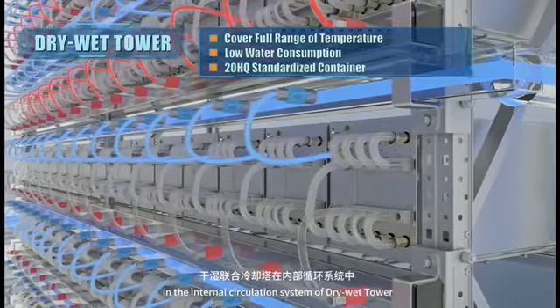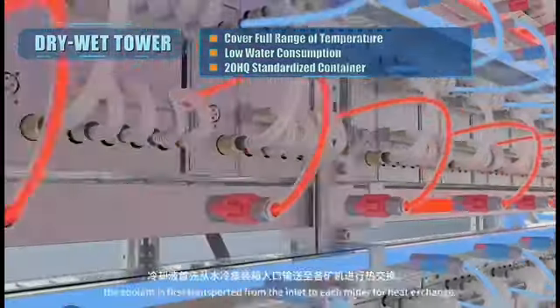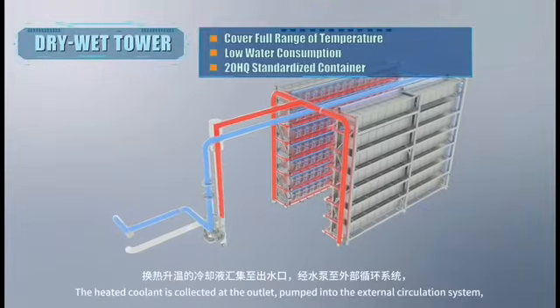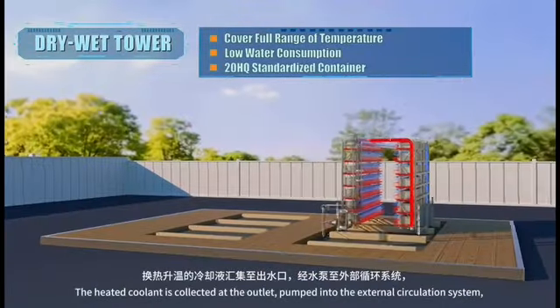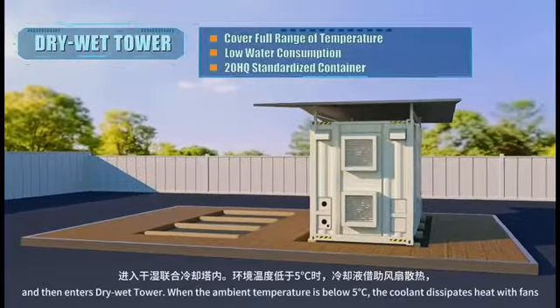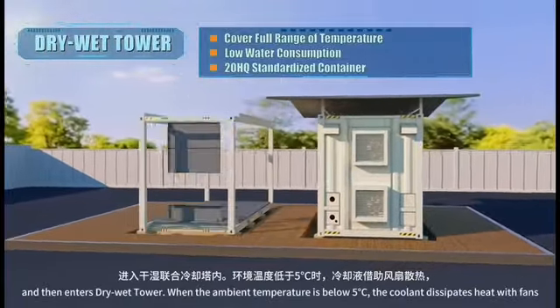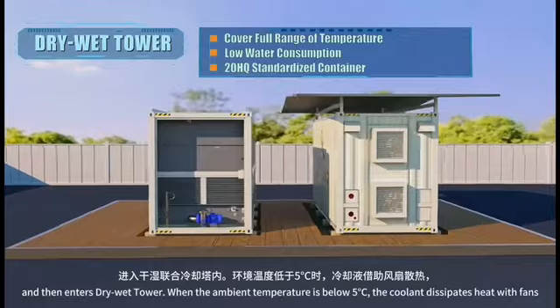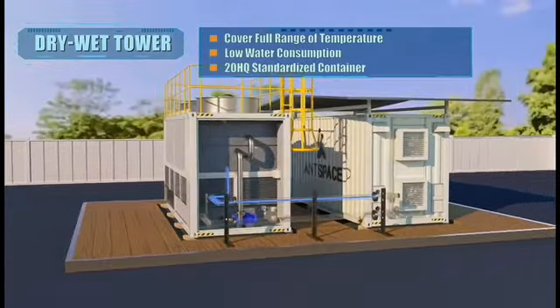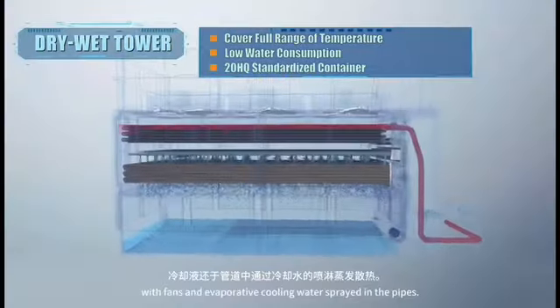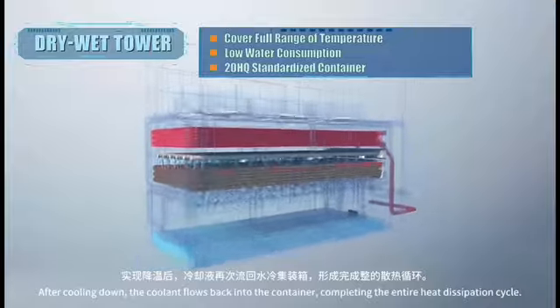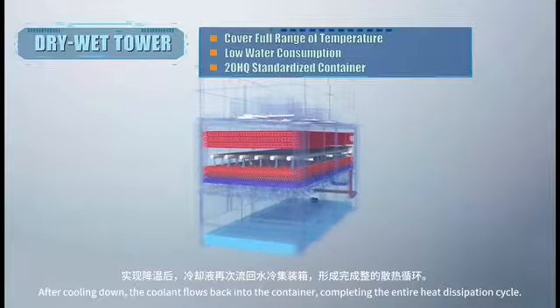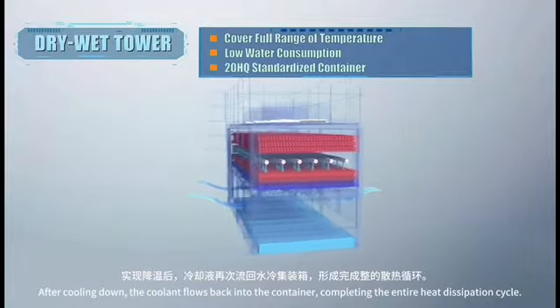In the internal circulation system of dry-wet tower, the coolant is first transported from the inlet to each miner for heat exchange. The heated coolant is collected at the outlet, pumped into the external circulation system, and then enters the dry-wet tower. When the ambient temperature is below 5 degrees Celsius, the coolant dissipates heat with fans. With fans and evaporative cooling water sprayed in the pipes. After cooling down, the coolant flows back into the container, completing the entire heat dissipation cycle.